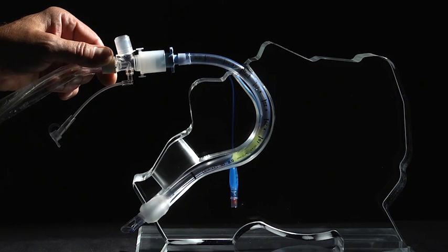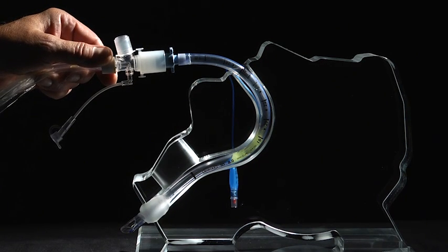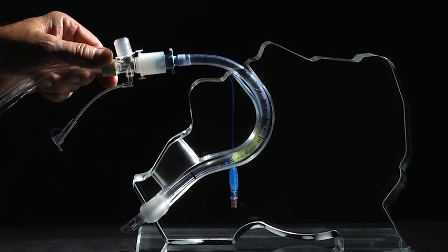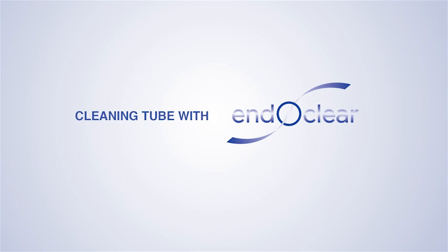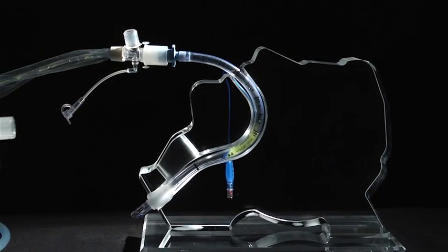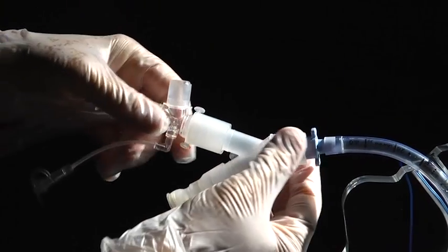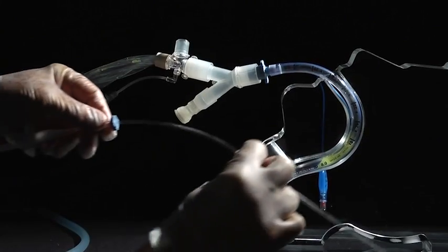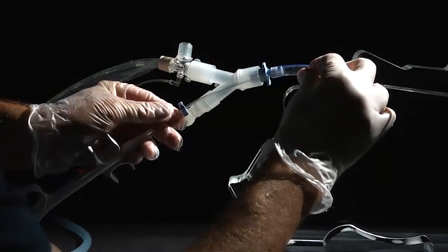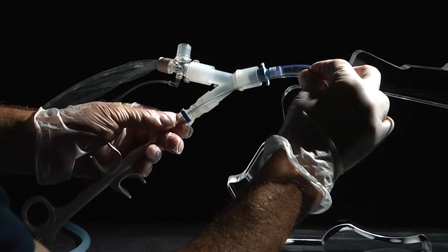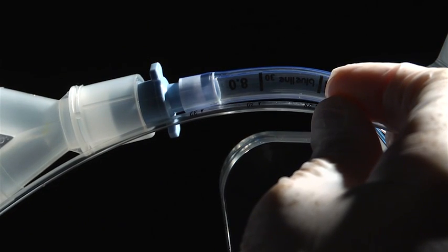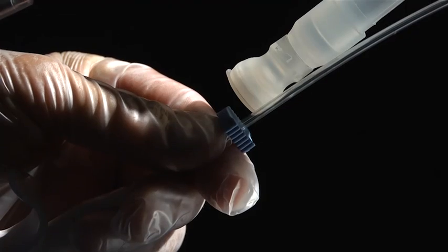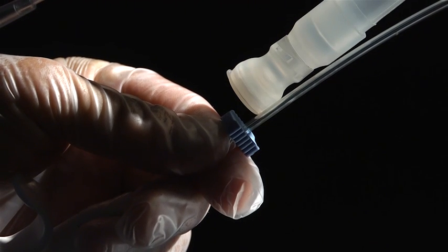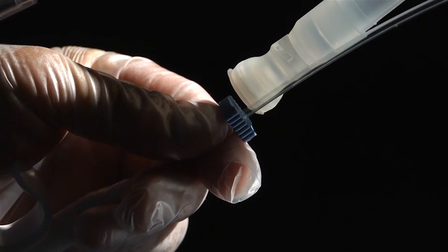Unlike in the see-through acrylic head model, once we've done 1, 2, or more passes with the suction catheter, we are unable to see what is remaining within the endotracheal tube if the tube is in the patient. To clean the tube with endOclear, we first insert the BCA adapter between the endotracheal tube and the ventilator circuit. Prior to inserting the device, we have to set the depth of insertion safety stop, and that's done by putting the centimeter markings on the device next to those on the endotracheal tube, and then moving the blue stop to the most proximal point of insertion at the BCA adapter.